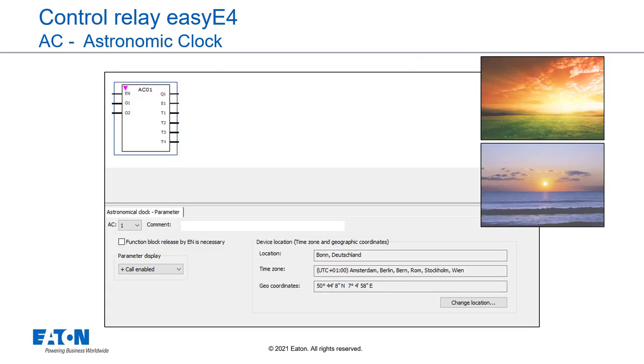Astronomic clock. easyE4 base devices provide 32 Astronomic clock function blocks, AC for short. The Astronomic clock function block calculates the sunrise and sunset times based on the geographical position of the device's location and the current device time. Both must be entered for the function block to work correctly.